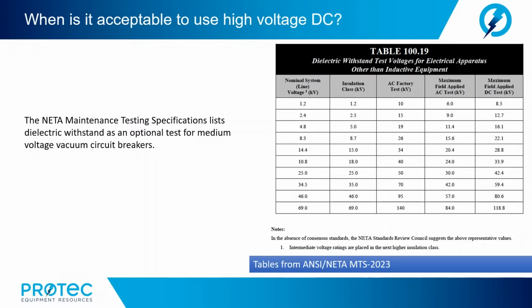However, note that the table does show that at the factory, the AC factory test voltage is given in the third column in, and then maximum field applied AC, and as an option if you are using DC, the final column would provide the DC equivalent voltages. So again, both AC and DC are found in table 100.19.